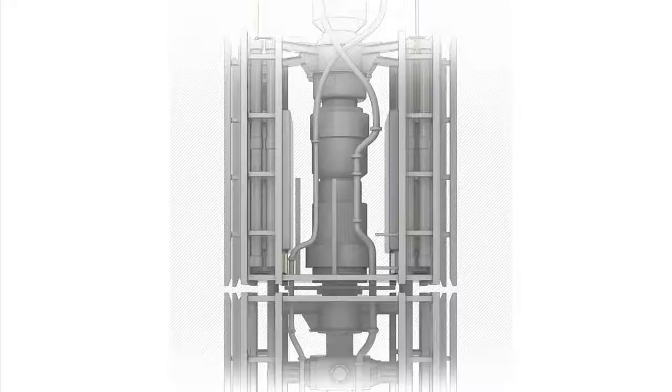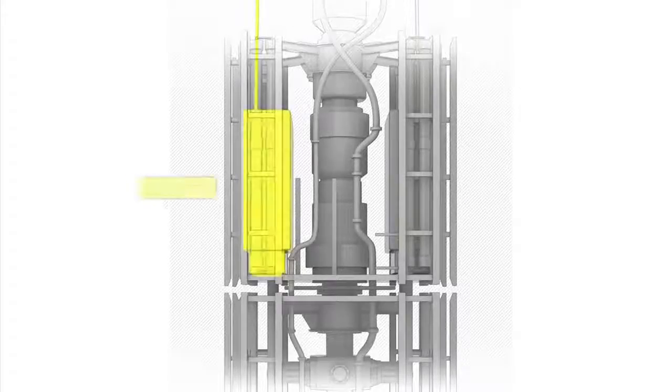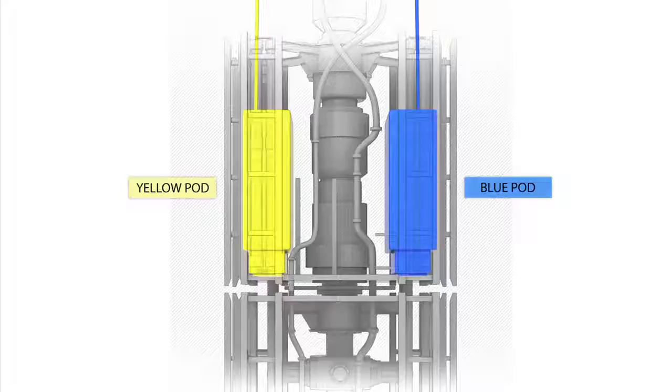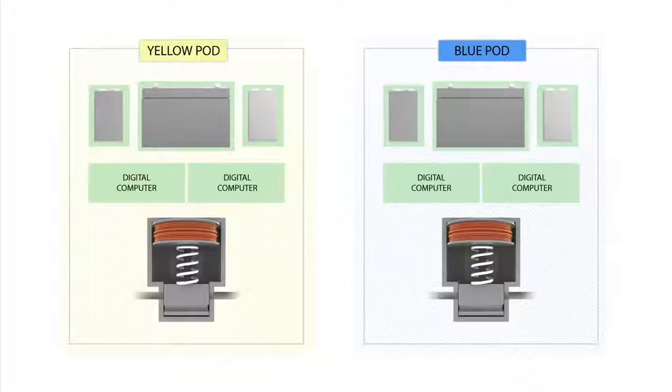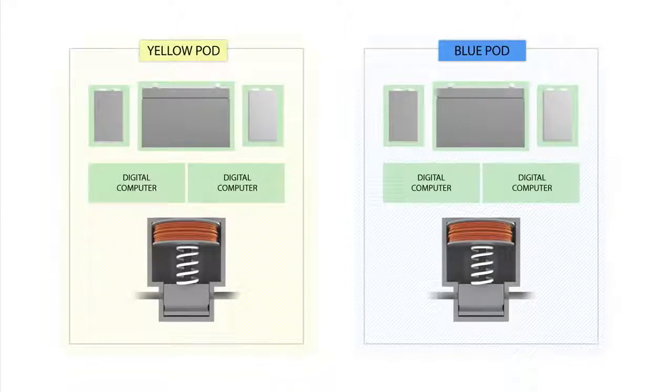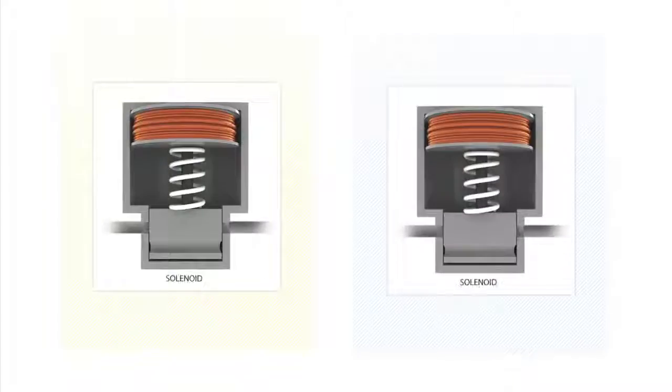The AMF Deadman system was operated by two redundant control systems on the BOP, known as the Yellow Pod and the Blue Pod. The redundancy is supposed to increase the reliability of the system in an emergency situation. The Yellow and Blue Pods worked independently of each other and were comprised of identical enclosed computer systems and sets of solenoid valves.